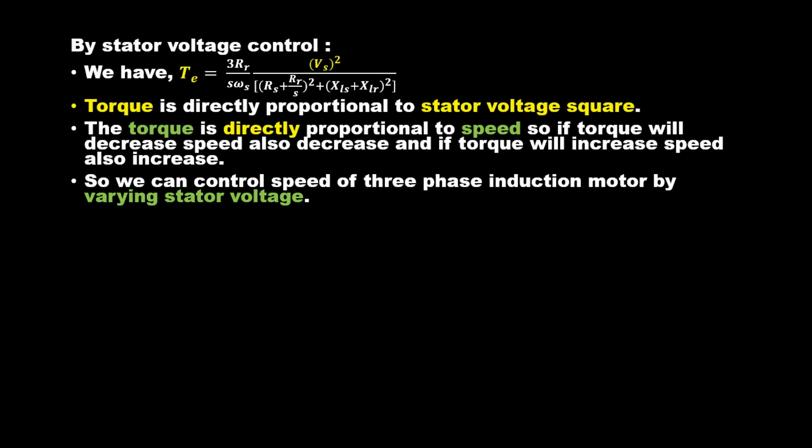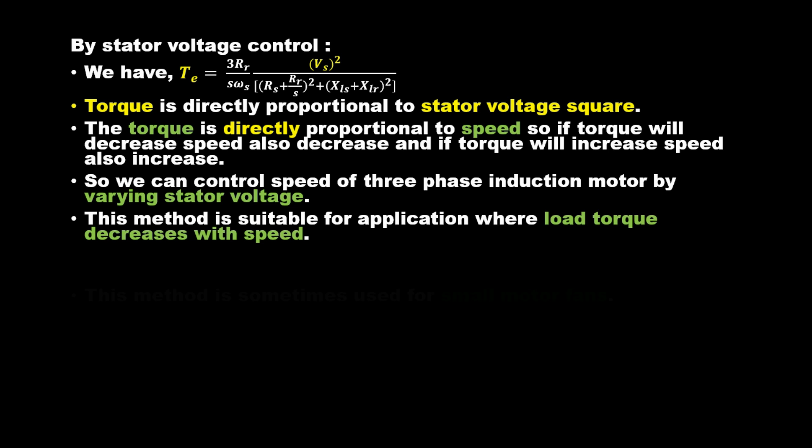So we can control speed of three phase induction motor by varying stator voltage. This method is suitable for applications where load torque decreases with speed. This method is sometimes used for small motor fans.